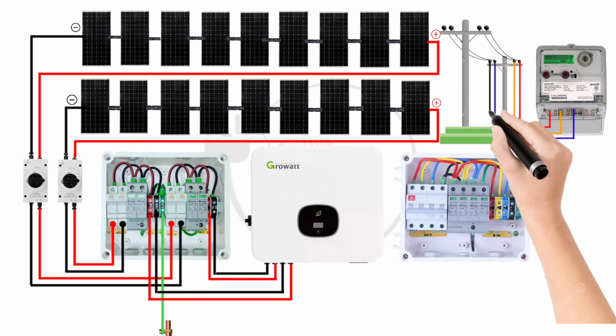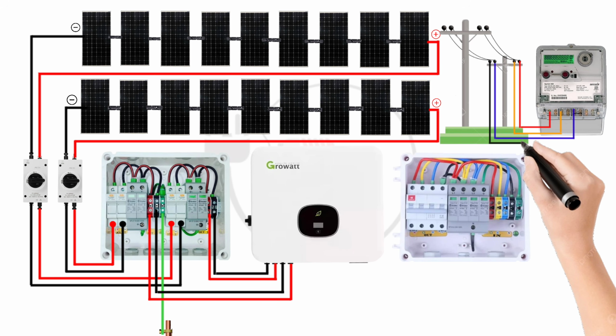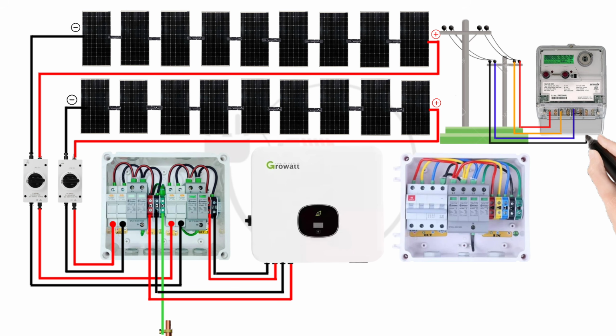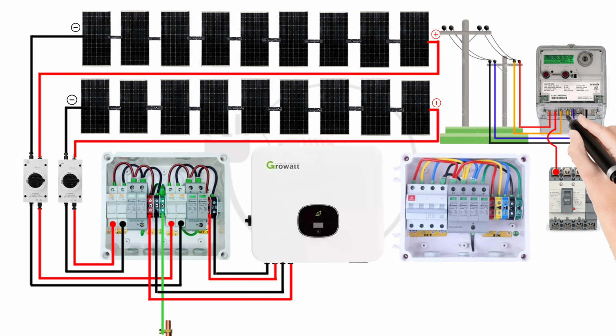It's crucial to match the phase correctly. The energy meter measures the electricity consumed. The output of the energy meter then goes to the input of the 4-pole AC disconnect switch. This switch allows us to isolate the solar system from the grid for maintenance or emergencies.